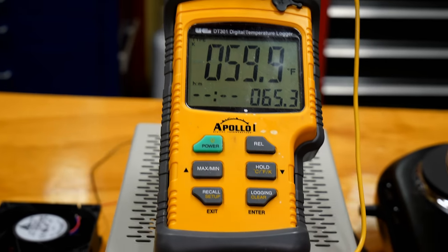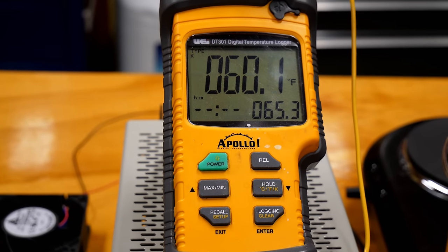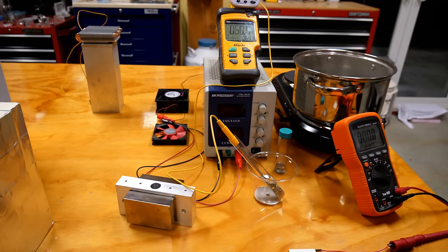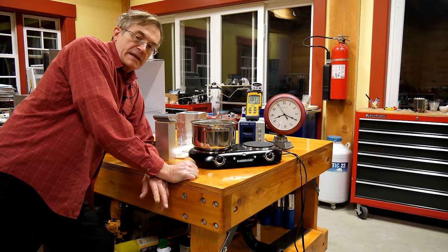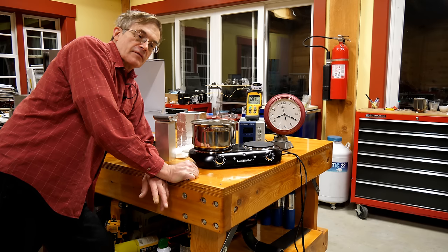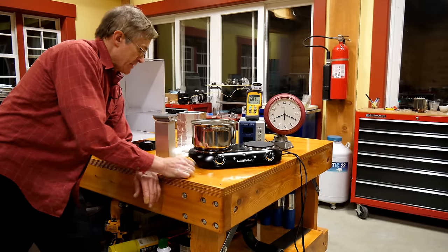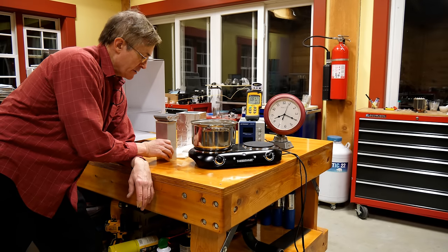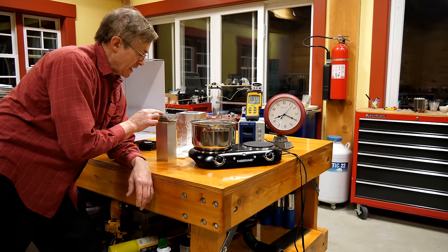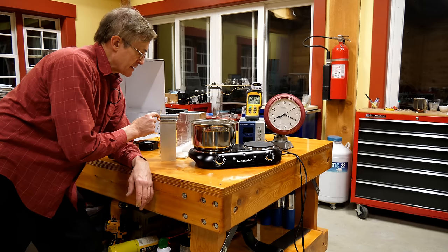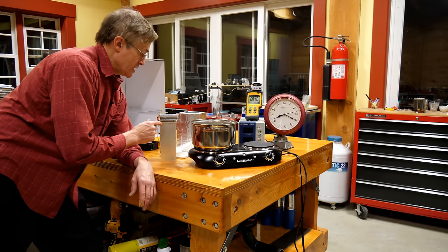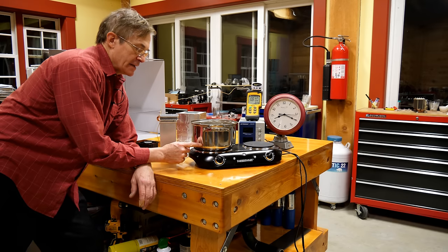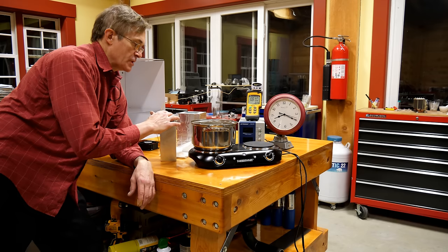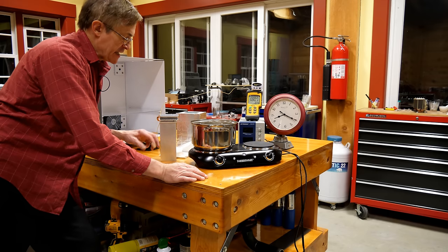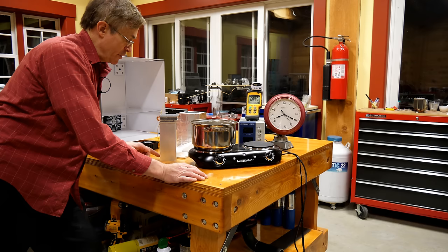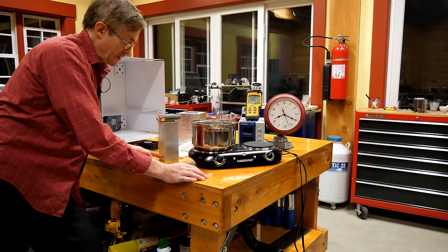Now I'm going to set up another example here to prove why it's important to balance all these different functions. I'm going to show you why it's important to balance the three legs of the heat extraction system. I have a 2.5 kilogram block of aluminum here that is bonded to a heat sink with a lot of fins and with some heat pipes to conduct the heat from the fins into the aluminum, or out. And what I'm going to do is dip this end only into this hot pot of water, and we're going to see how long it takes for the temperature to begin to distribute down to the thermistor that I've bonded all the way at the other end of this block.